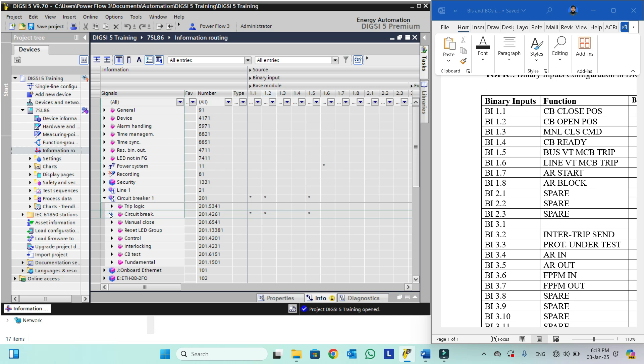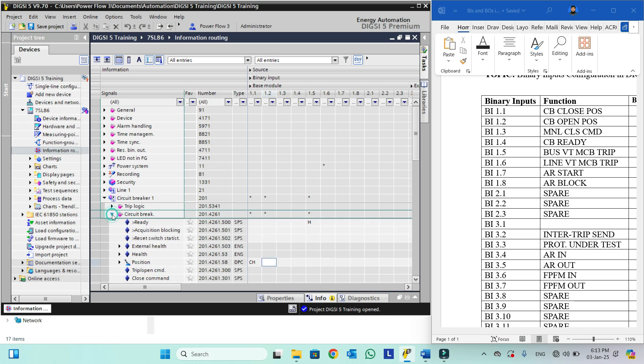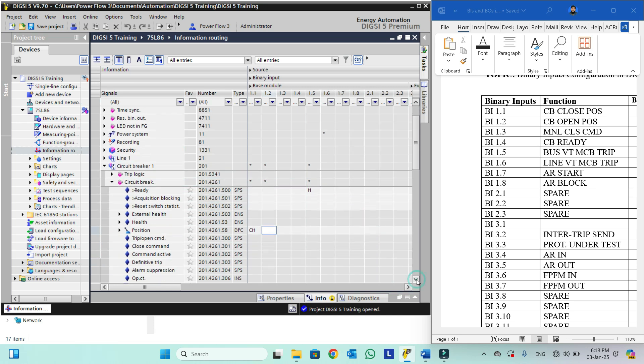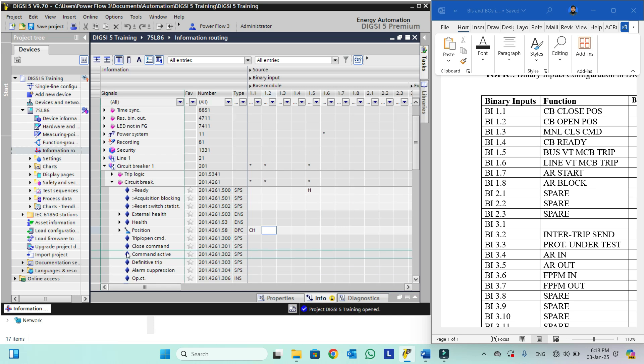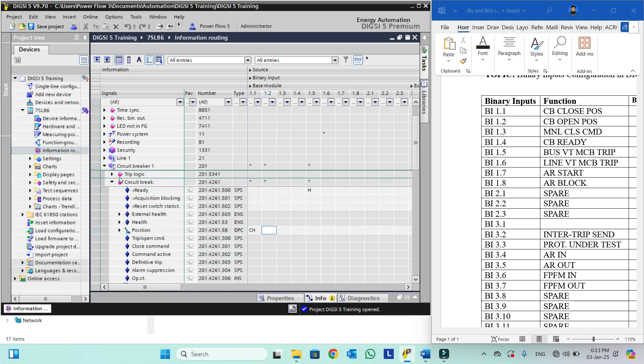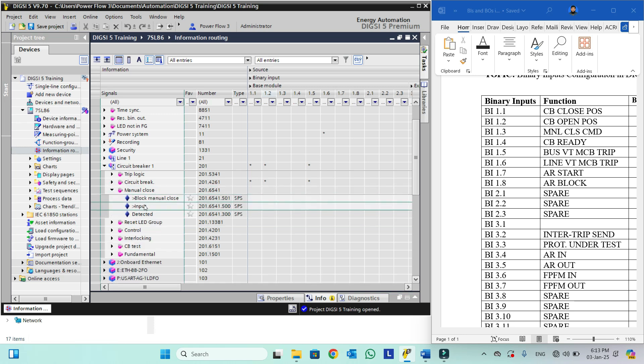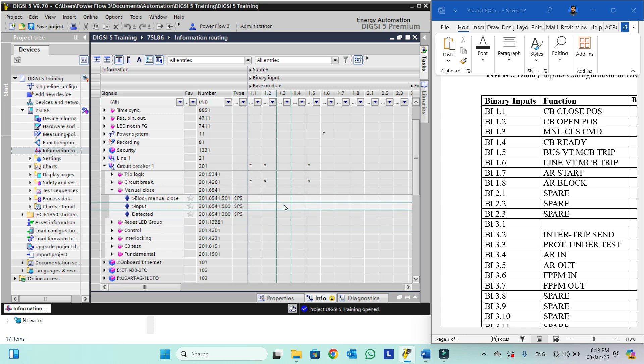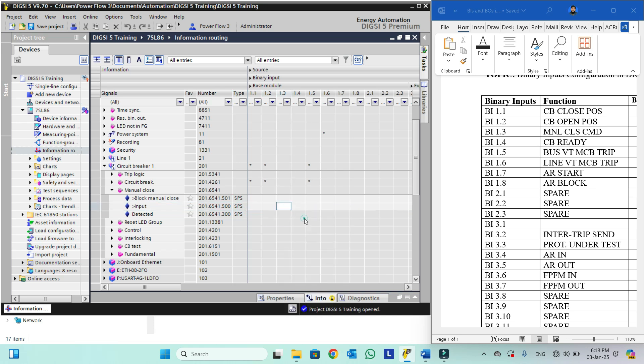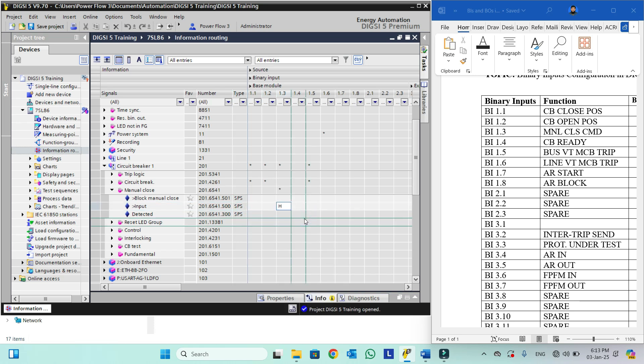Binary input 1.3 is manual close command. Sometimes we need this manual close command to initiate our SOTF. So we will go into manual close. Here you can see there is an input available — this input is actually the manual close command. We will make it H, meaning when voltage comes it will be active.